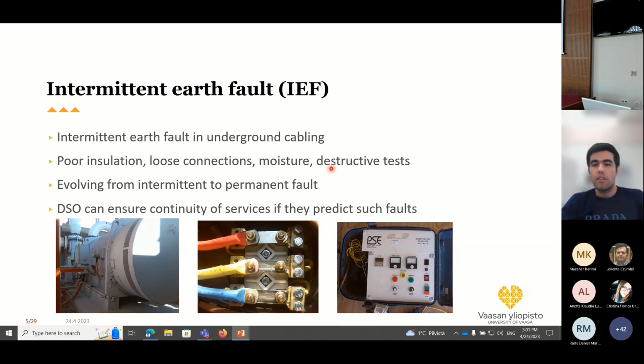And another reason is destructive tests. For cable, we have two different tests. One of them is a Megger test, which is used to be sure about continuity, and most of the time it lasts, for example, 30 seconds or 1 minute, and for a high-level cable maybe more than that. And we also have a HiPot test, which is about being sure about insulation, for MV cable. Most of the time it lasts about 15 or 30 minutes, and we inject maybe 2.5 times the nominal voltage to be sure about the insulation. However, they are destructive, and they may cause intermittent earth fault.